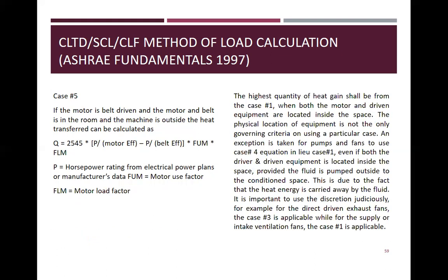Case 5. If the motor is belt driven and the motor and belt are in the room and the machine is outside, the heat transfer can be calculated as, ito, 2545 times P over motor efficiency minus P over the belt efficiency times FUM times FLM. P is the horsepower rating from electrical power plans or manufacturer's data. FUM is the motor use factor. FLM is the motor load factor.